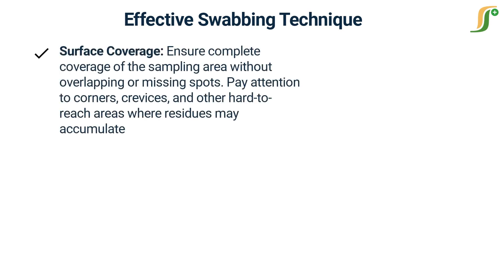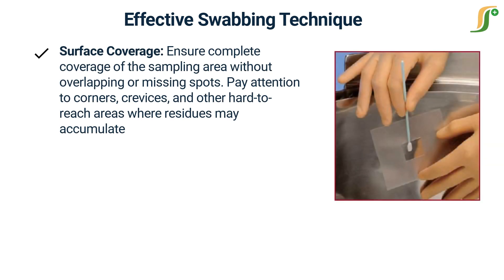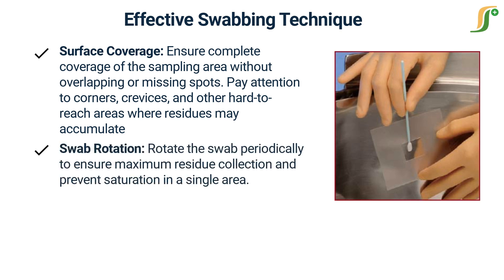Surface coverage. Ensure complete coverage of the sampling area without overlapping or missing spots. Pay attention to corners, crevices, and other hard-to-reach areas where residues may accumulate. Swab rotation. Rotate the swab periodically to ensure maximum residue collection and prevent saturation in a single area.